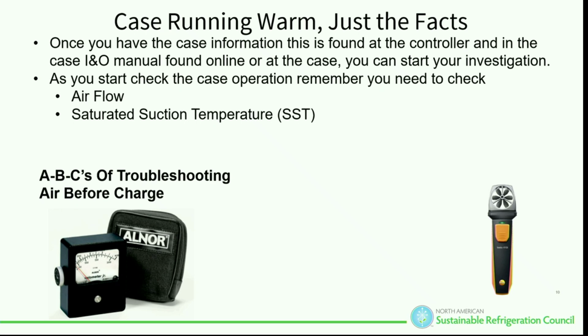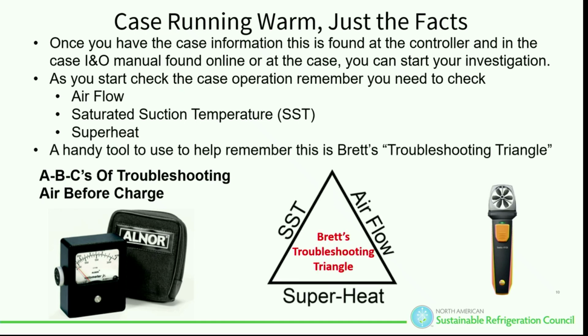If that fan is moving way too fast, it could potentially raise the pressure, which is going to throw off your saturated. All right. Same thing with the next thing that we're going to talk about, which is superheat. Once you have your airflow correct and the saturated suction is exactly where, or at least within 2 to 3 degrees of what it's spec'd for in that IOM manual, the next thing to check is the superheat. It's really easy to do.